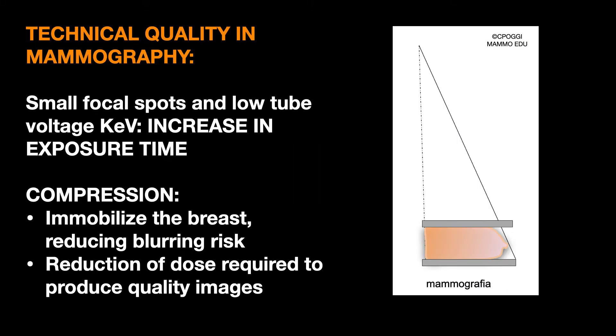Small focal spots and low tube voltage impose an increase in exposure time. Compression allows to immobilize the breast, and thus decrease the blurring risk. The thickness reduction also decreases the dose required to produce a high-quality image.